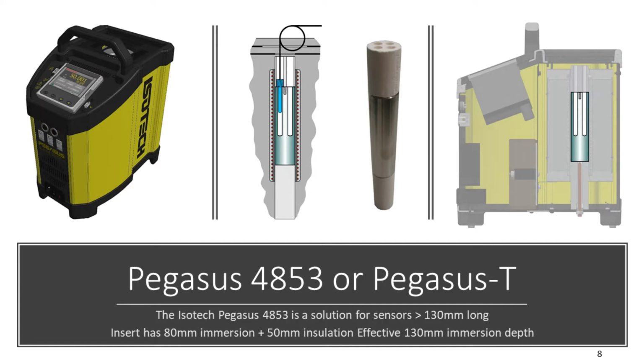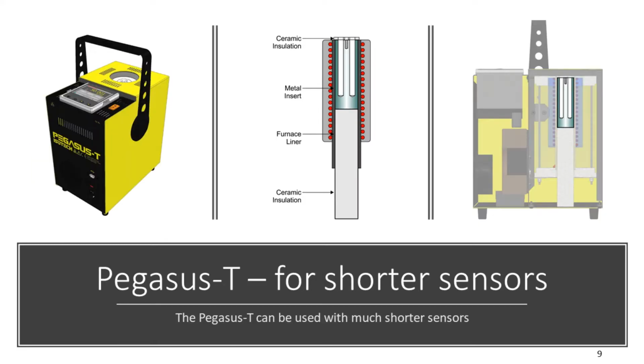Isotech have two solutions for calibrating shorter sensors to high temperatures: the Pegasus 4853 and the new Pegasus T. The Pegasus 4853 is a solution for sensors that are longer than 130 mm. The furnace insert has an immersion of 80 mm, and 50 mm of insulation provides an effective immersion depth of 130 mm. The Pegasus T has been developed with much shorter sensors in mind.